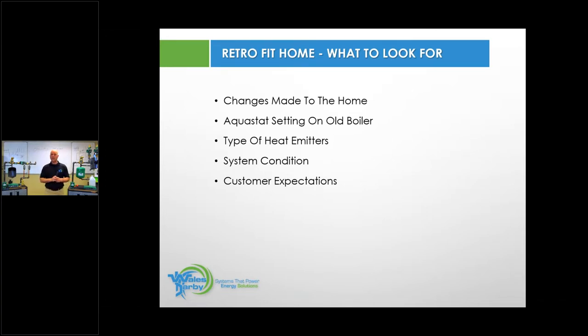In that retrofit home, what do I look for? Changes to the home. That's a great conversation to have with the homeowner while you're walking the job. What changes have they made to the home? Did they insulate? Did they put new windows in? Did they put vinyl siding on? This will all reduce what companies use as the K factor of heat loss, basically to the outside. That'll make the home use less fuel.